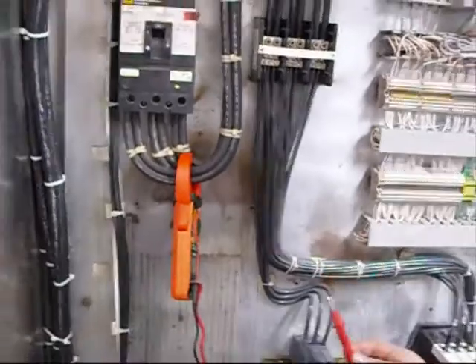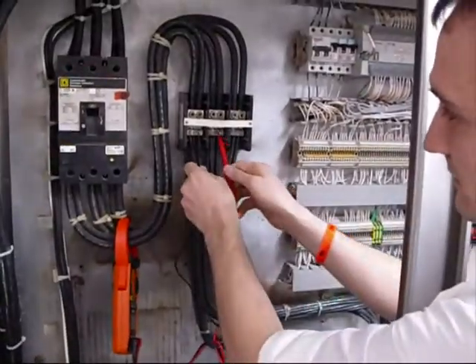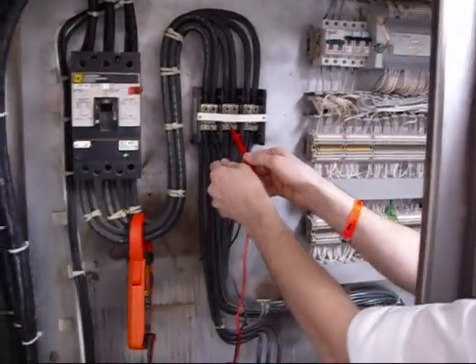Okay, so now we're going to select the voltage. We've selected voltage. We're on DC. We need to press the mode button to take it to AC. And now we're going to test the voltages. Now I'm going to connect across 2 of these phases. I'm going to hang the meter off a suitable cable so we can read what it's saying. And if we zoom into the actual meter, we can see we've got 450 volts. So this is okay.